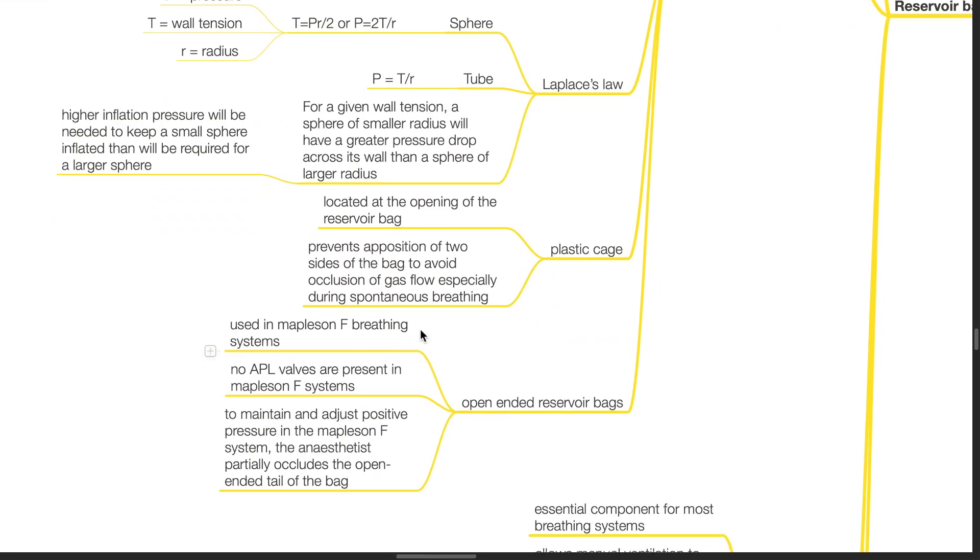The reservoir bag has a plastic cage located at the opening of the reservoir bag. This plastic cage prevents apposition of two sides of the bag to avoid occlusion of gas flow, especially during spontaneous breathing.